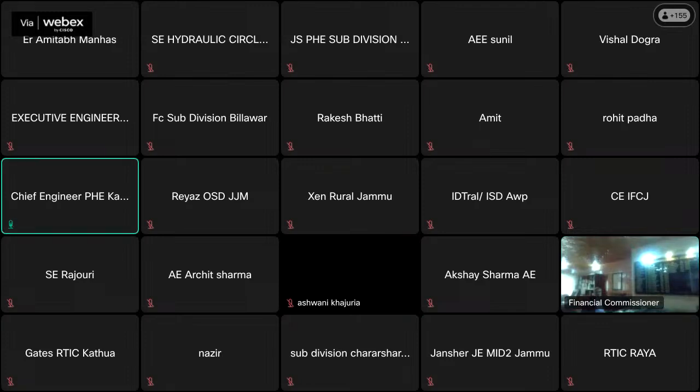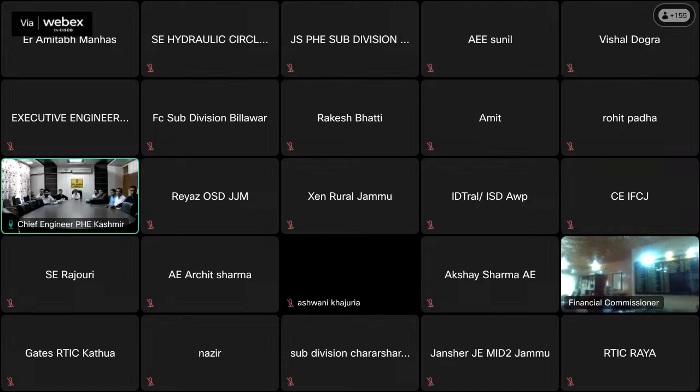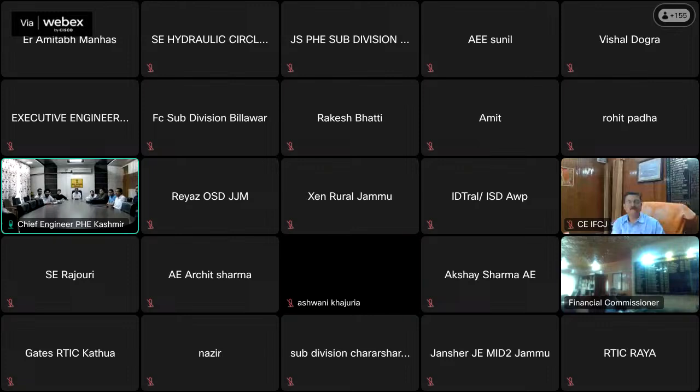Yes, sir. The question to Mr. Akshay Sharma is asking about where to use the LT motors and where to use the HT motors. बोलिए, आप बहुत माइक से दूर हैं. हाँ जी. Sir, up to 350 HP, the LT motors are used. Thereafter, the efficiency of the LT motors is reduced. So the HT motors are preferred after 350 HP.